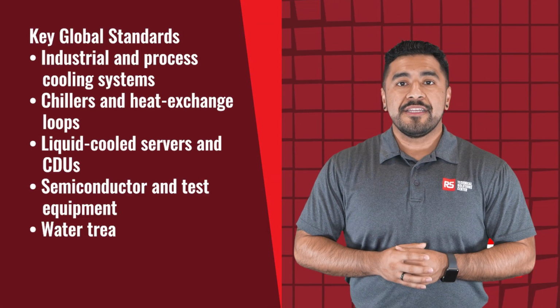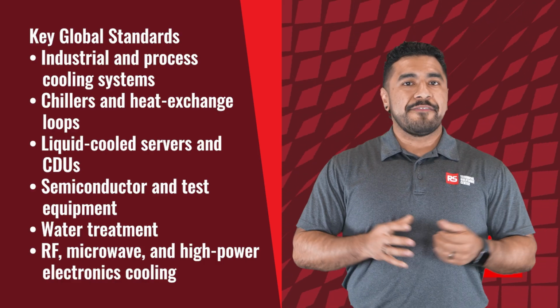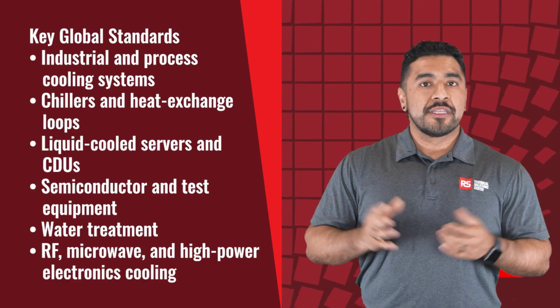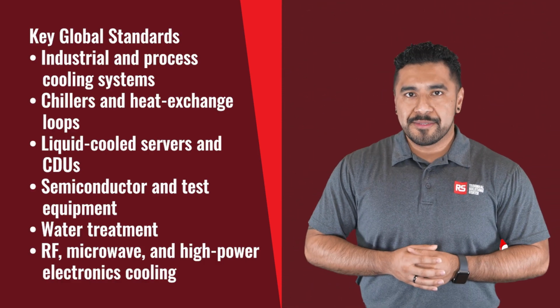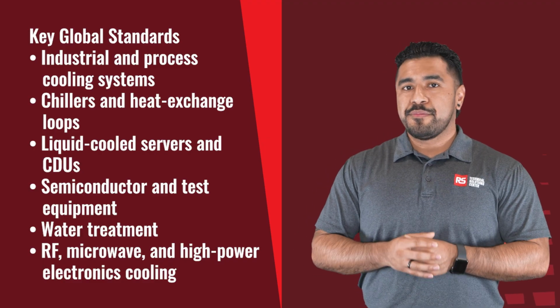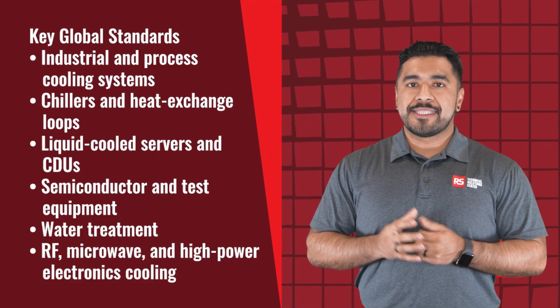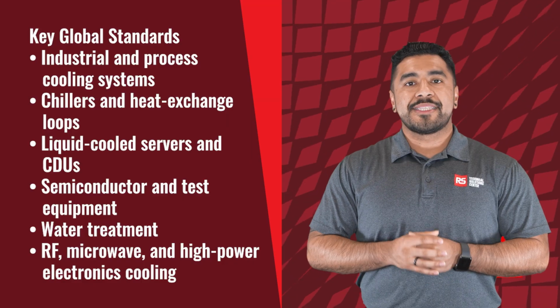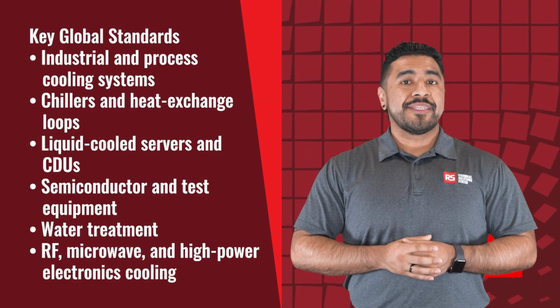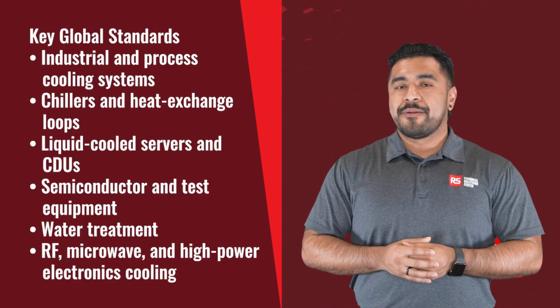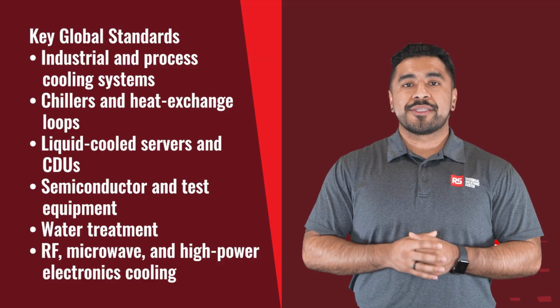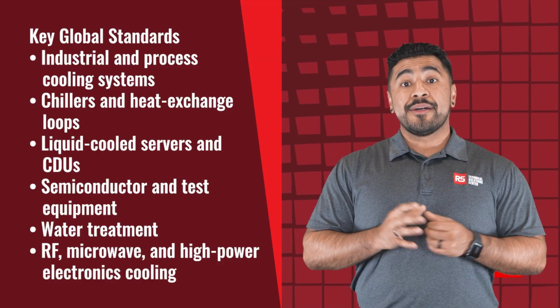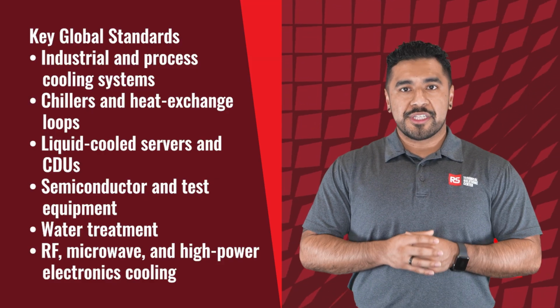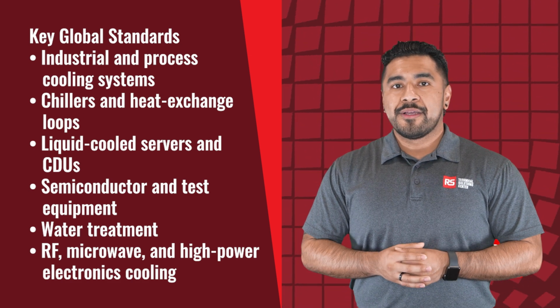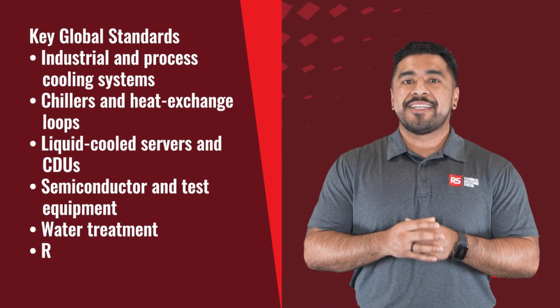You'll find the XFT used across industries where uptime, safety, and easy retrofits matter, such as industrial and process cooling systems, chillers and heat exchange loops, liquid-cooled servers and CDUs, semiconductor and test equipment, water treatment systems, and RF, microwave, and high-powered electronics cooling. Because it installs externally and has no flow obstruction, it's ideal for critical equipment where shutting down the line just isn't an option.